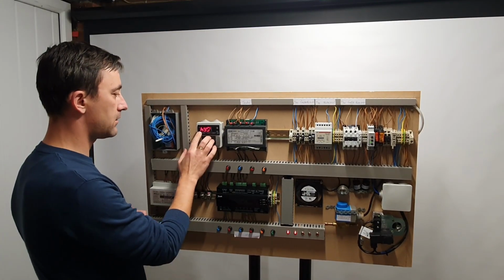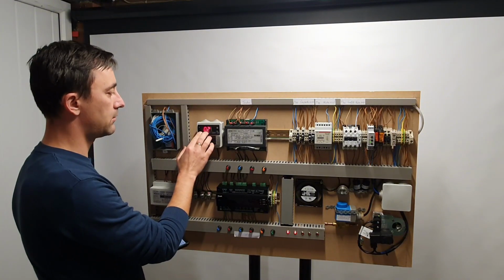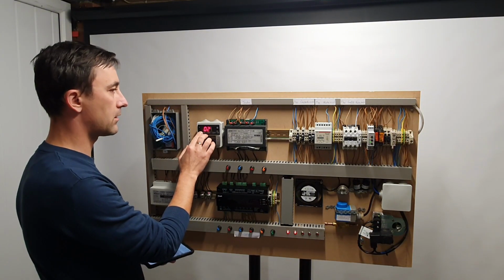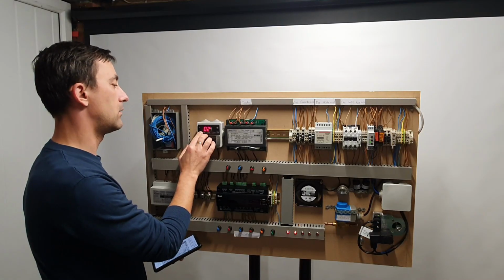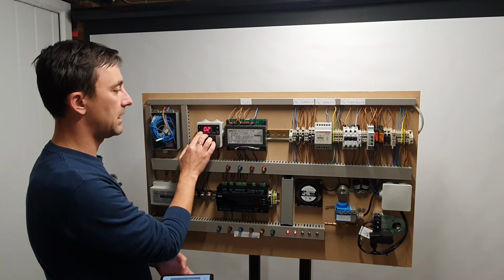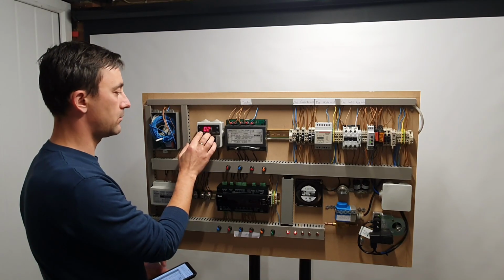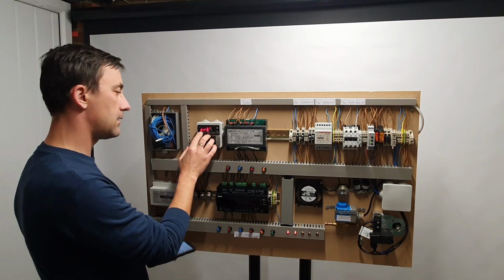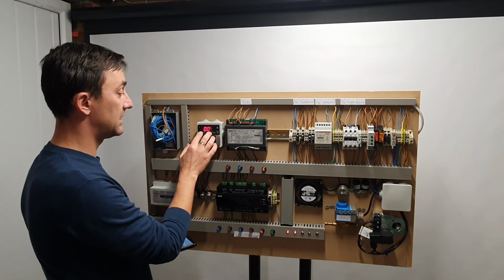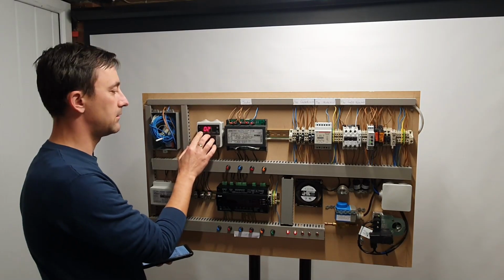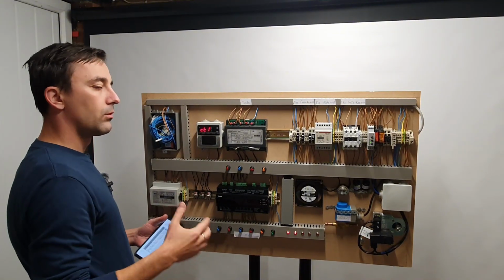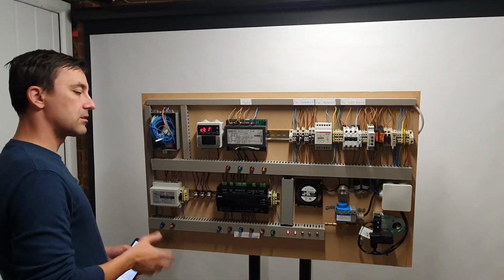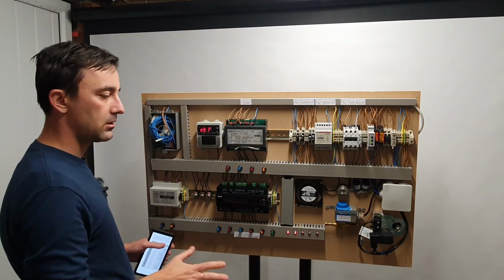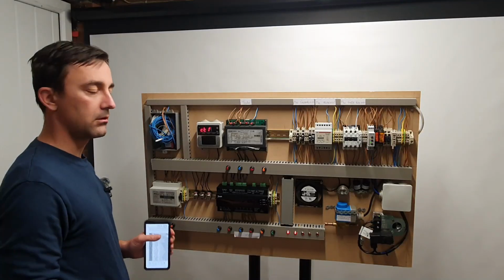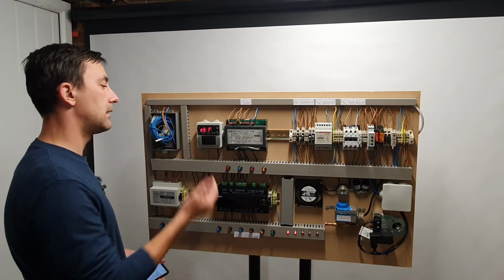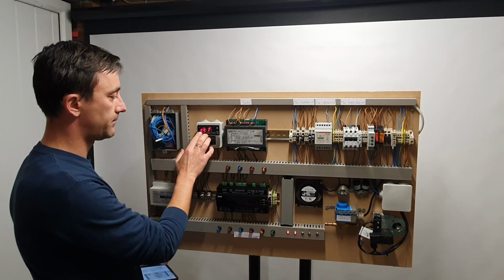There we go. Hysteresis or differential 2 degrees. I can leave that as 2. So it will work between -18, where the compressor will cut off, and -16, where the compressor will cut in. CRT is compressor rest time, set as 0. I shall put this to 2 minutes because you don't want the compressor to short cycle in case you have a spike in the temperature reading. So achieve set point, leave the compressor be for a minute or 2, and then it can start again.